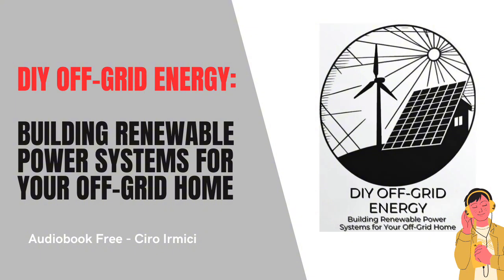Working with batteries presents its own set of safety challenges. Batteries, particularly lead-acid and lithium-ion types, contain chemicals that can be hazardous if mishandled. Proper ventilation is essential to prevent the buildup of explosive gases, particularly hydrogen, which can be released during charging. Battery enclosures should be fire-resistant and include venting systems to safely expel gases. Protective gear, such as gloves and safety glasses, should be worn when handling batteries to avoid contact with corrosive electrolytes.